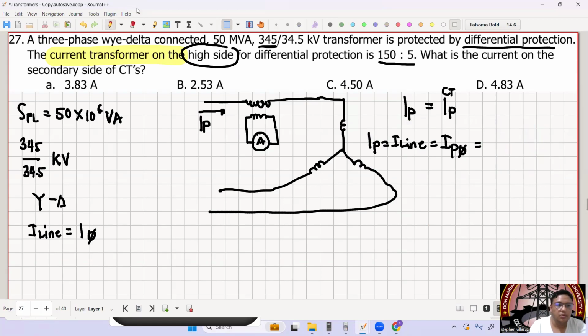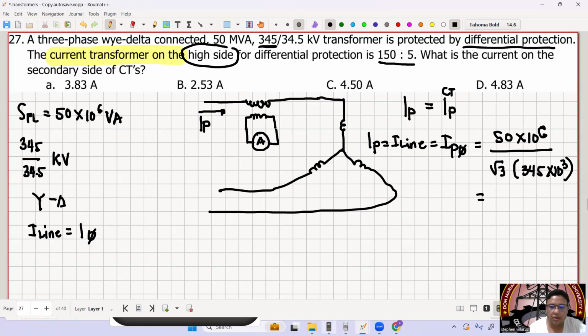This is equal to 50 MVA over square root of 3 multiplied by the primary voltage, 345 kilovolts. So that is 50 mega over square root of 3 times 345 kilo, which equals 83.674.